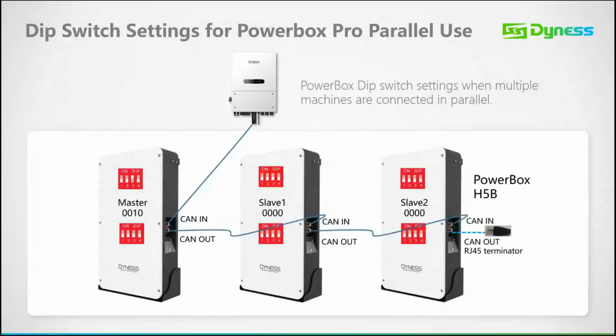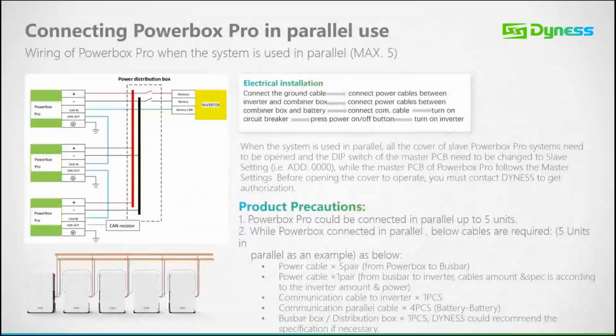Regarding your communication cable, it's from your inverter to your master Powerbox Pro, from your master Powerbox Pro out to your slave in, from slave out to slave in of your second slave, and so forth and so forth. Connecting Powerbox Pro in parallel use. So when connecting 2 or more Powerbox Pros, again, a bus bar needs to be used, and the bus bar needs to then be rated to each system specifications.